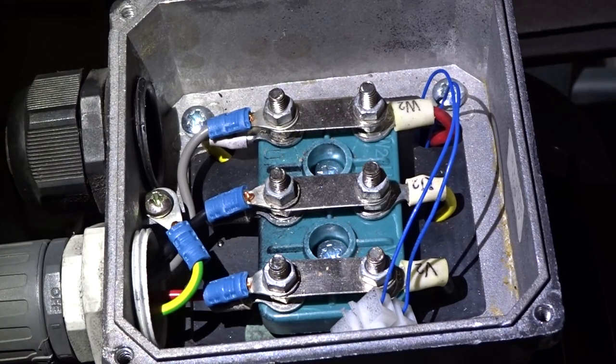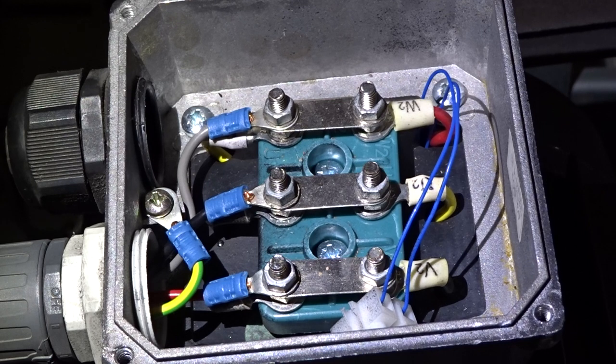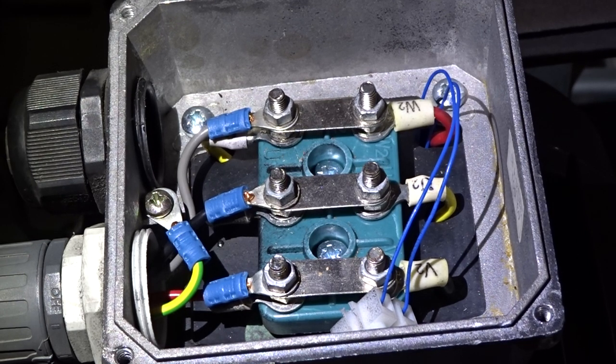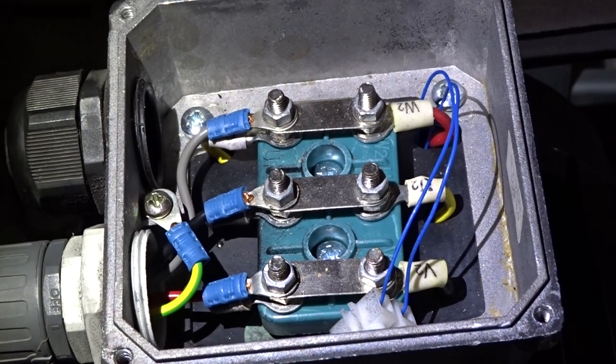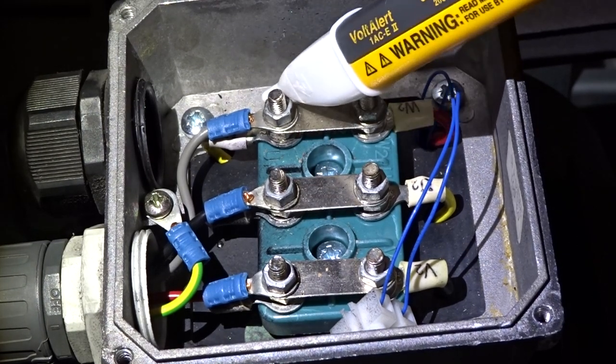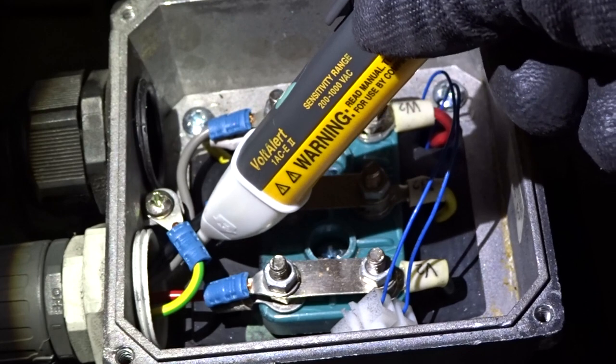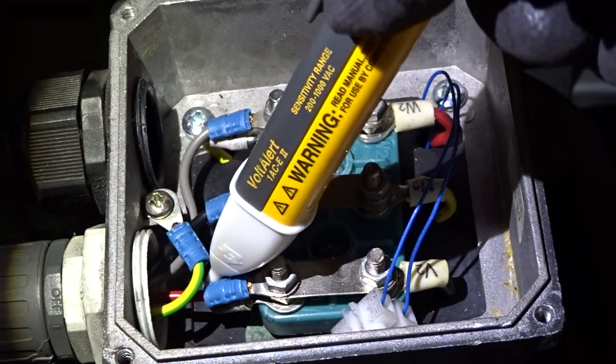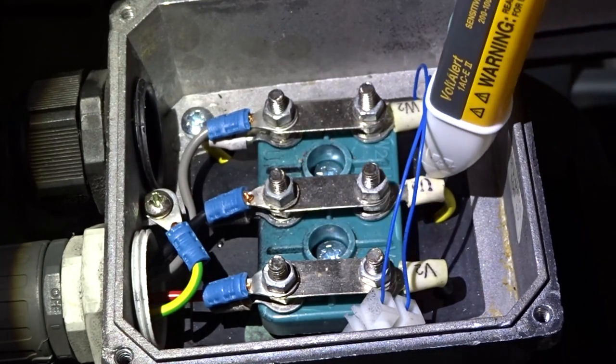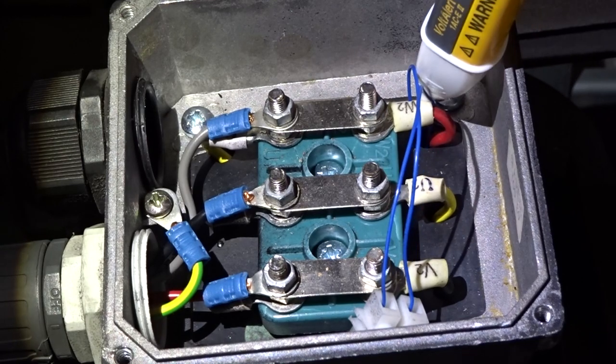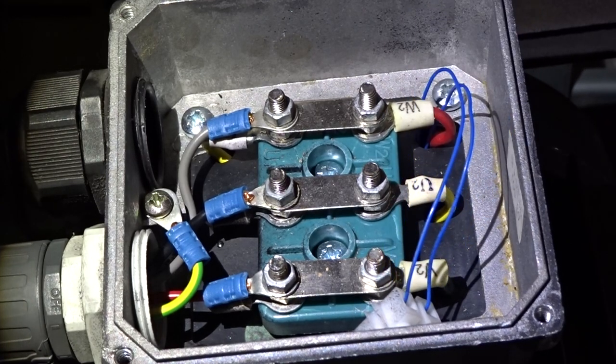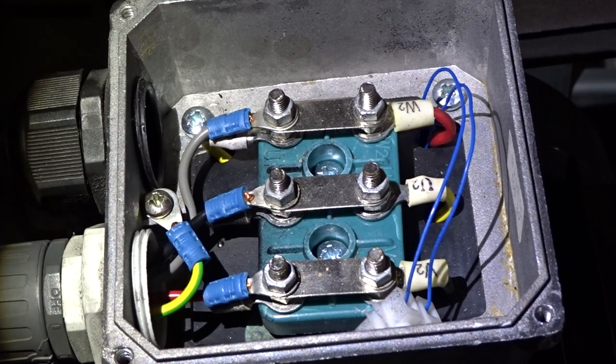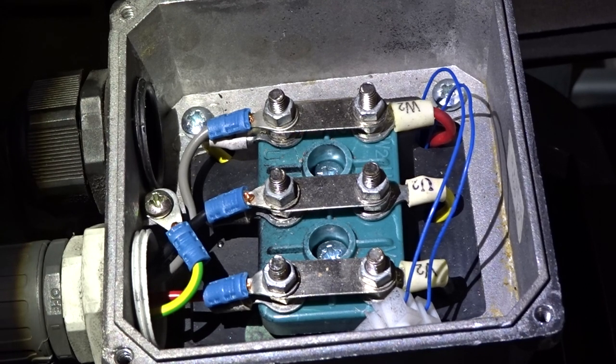So here we are now guys, the top of the cover has now been removed from the wiring harness at the motor. So all we're going to do is with our voltage pen, just test to make sure that there is no power going to the fan, to the motor. It has been isolated twice. It has been isolated at the panel and it's also been isolated at the fan's isolation point. It's been locked off and tagged off.